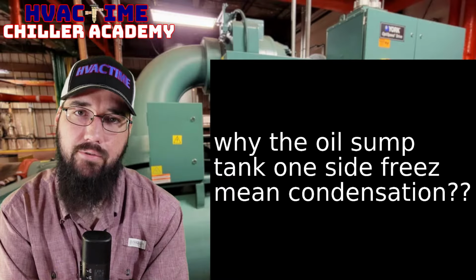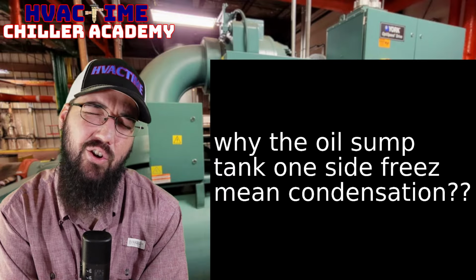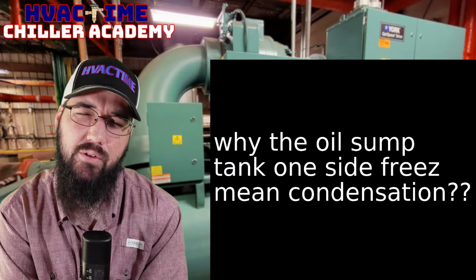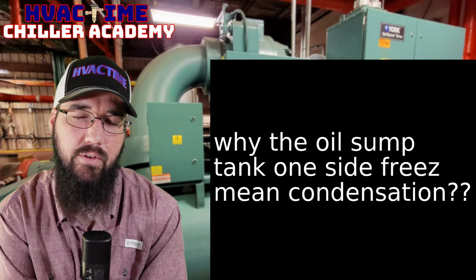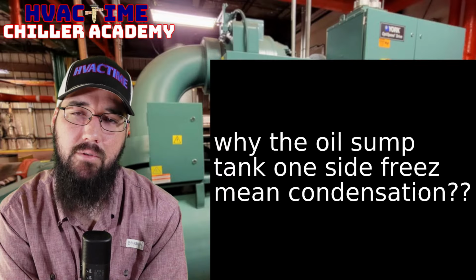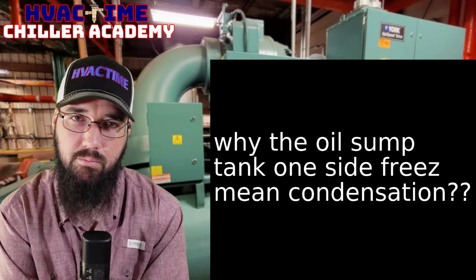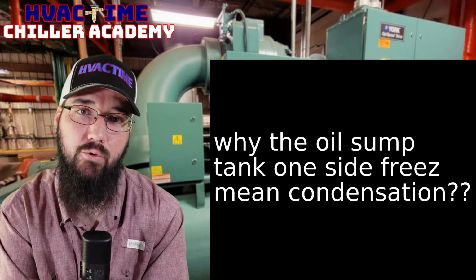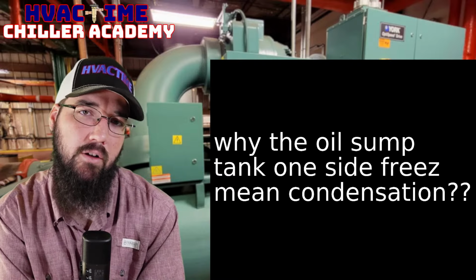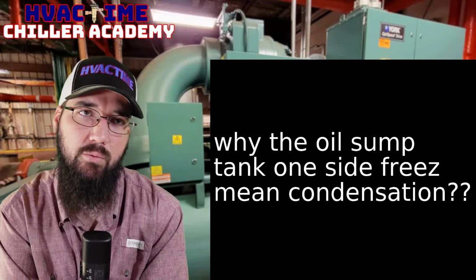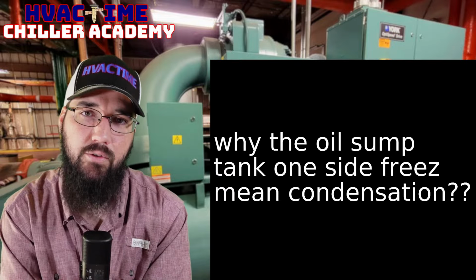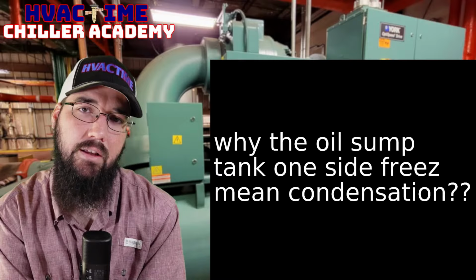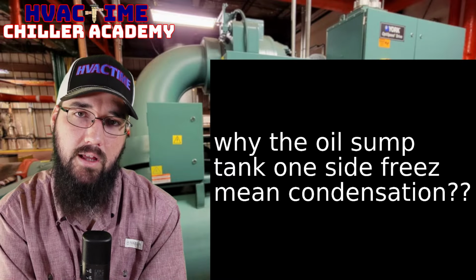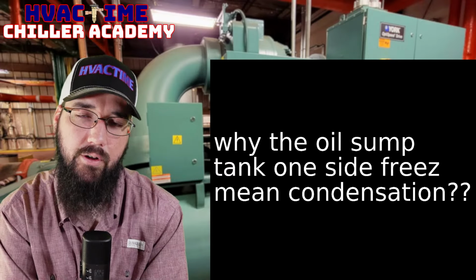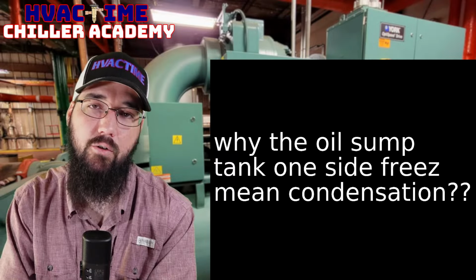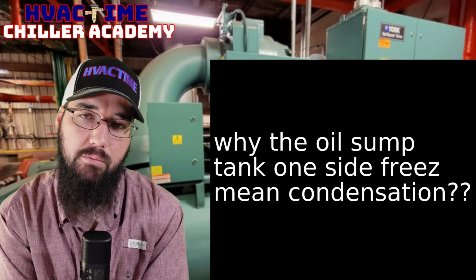When your eductor and that filter block begin to ice over, it could be that the filter is beginning to clog up. That's something to be aware of. If that is true, then you're going to see a lot of oil migration issues, just because you're not flowing correctly from the evaporator to return your oil. So that's something to look for. But most commonly, in my experience, it's not because the filter is clogged. It's because we're overfeeding the eductor assembly from the evaporator oil return circuit, because that valve is open too much, and we need to close that valve down a little bit so that the eductor block stops freezing.